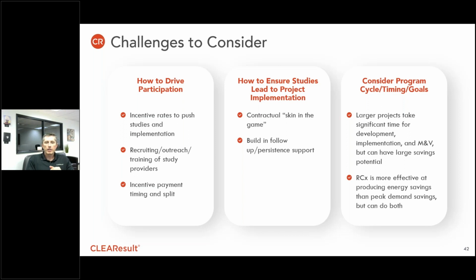Retro commissioning is most effective at energy savings, though it can also produce peak demand savings. Many measures focus on optimizing consumption and reducing energy waste during lightly loaded periods or shoulder seasons, so it often results in more energy savings than peak demand savings. But both are opportunities, on both the electric and gas side.